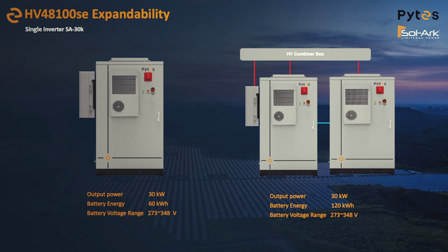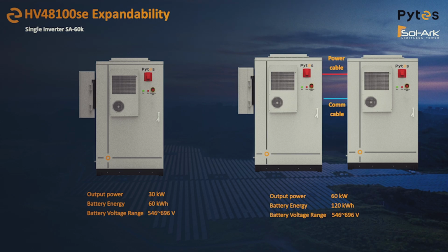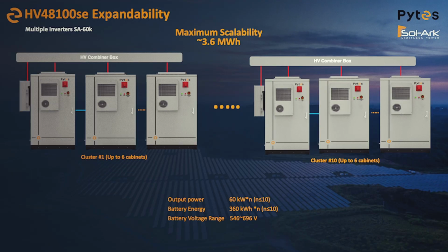The PCS, or the inverter, mounts right on the side, as you can see right there. And then really for me, the only difference to point out here is when we look at a 30K versus a 60K inverter. Remember, because we've got 2 parallel strings within each battery cabinet, 1 battery cabinet with 2 parallel groups, we're already using both of the inputs on the inverter. So if we have a second cabinet with another 2 parallel groups, now we've run out of inverter inputs, and now we're using our combiner box. 60K is a little different, right? Because with 60K, you can have 2 cabinets with 12 batteries in each, and then each cabinet feeds directly into one of the inputs on the inverter. So it's a little bit simpler, I think, but you can do kind of the same thing at the end of the day.